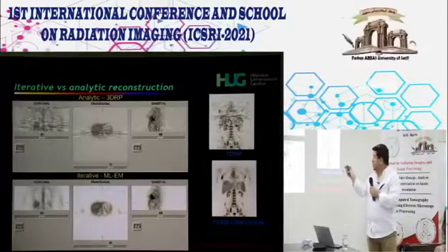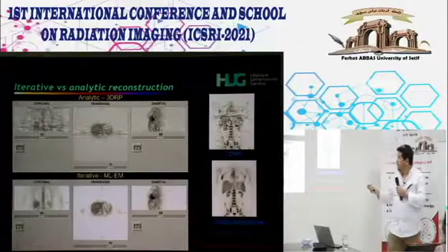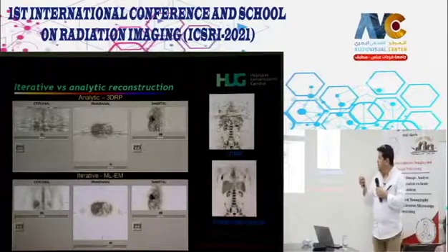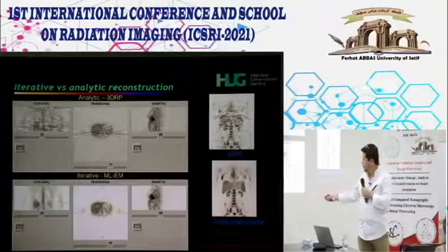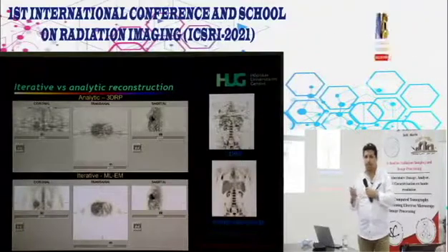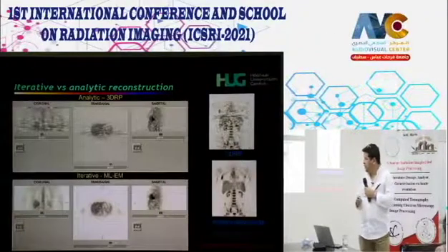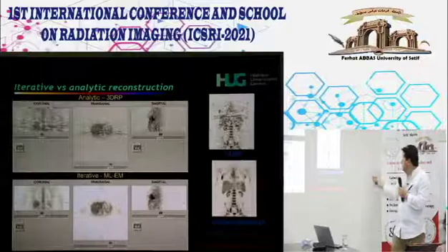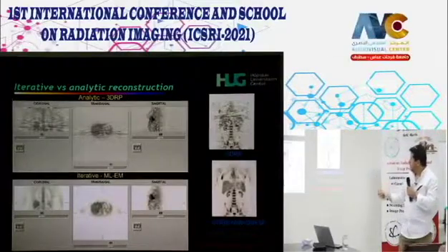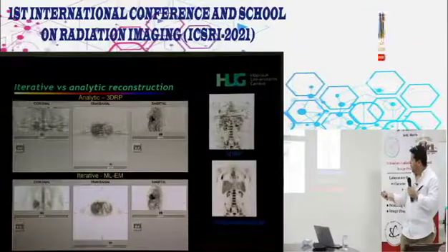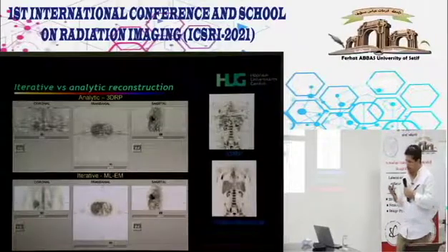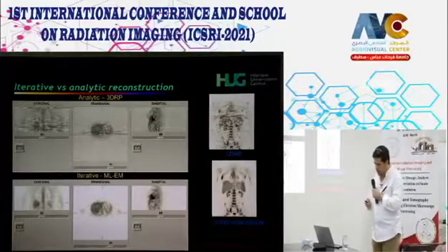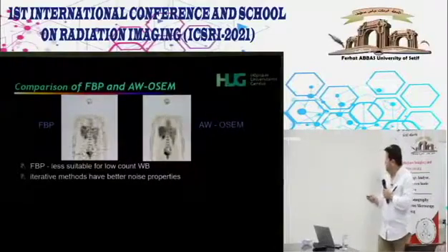What is important here is to show you some clinical images comparing conventional filtered back projection, which generates images of extremely low quality, and the advantage of iterative reconstructions, which produce images of much improved quality. And again, this is not really state of the art, so this was produced basically in 97, 98. And you can appreciate here also the better image quality produced with iterative reconstruction techniques, in the sense that the noise and the significant artifacts that you see in conventional filtered back projection are removed, and you see the same effect here.